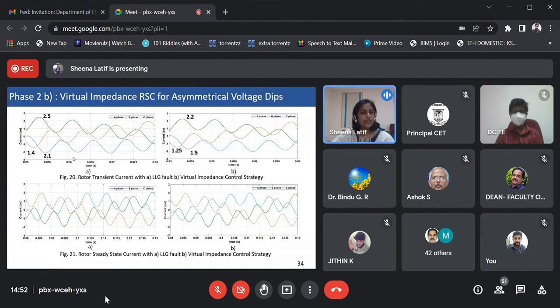Now, the same virtual impedance RSC control strategy is applied for an asymmetrical voltage dip condition, a double line to ground fault. The rotor transient and steady state currents during the double line to ground fault, without and with the virtual impedance, are shown. We can see that in the transient period, the virtual impedance method has its own contribution in reducing the transient peak values of rotor current, while in the steady state period, the virtual impedance control strategy does not have much impact on the steady state rotor current reduction or its harmonics.